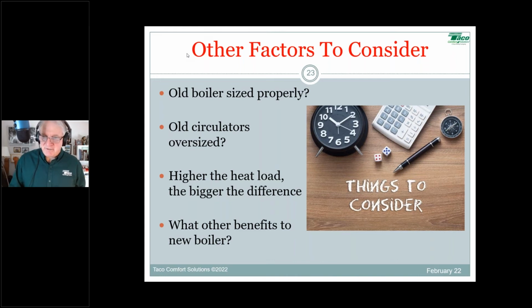It's an air-to-water heat pump called the Taco System M, and it's modular. We've got an outdoor unit and a factory-made, wired, and ready-to-go indoor unit that includes your circulators, your buffer tank, the entire control strategy, everything, all set up and wired. All you need to do is run power to the outdoor unit, power to the indoor unit, 6 piping connections, 2 piping connections to connect the indoor to the outdoor unit with water. The outdoor unit is a monoblock system, so the outdoor unit refrigeration is all factory sealed.